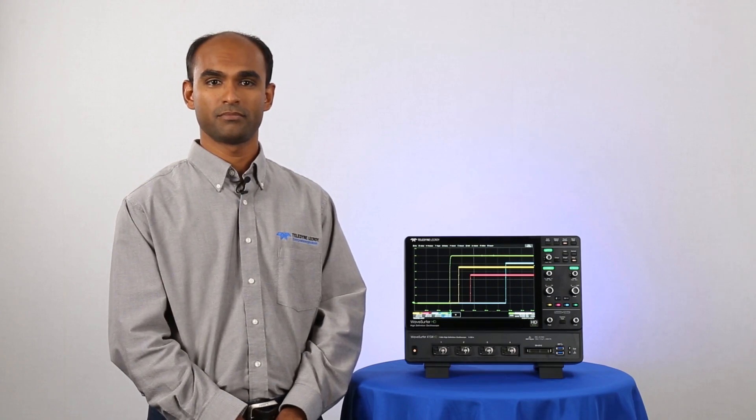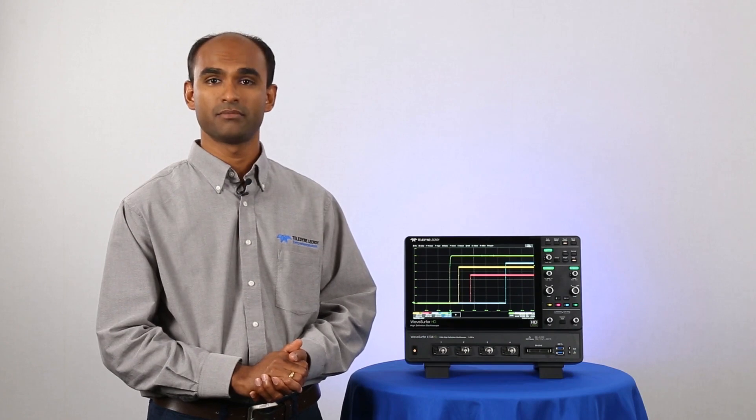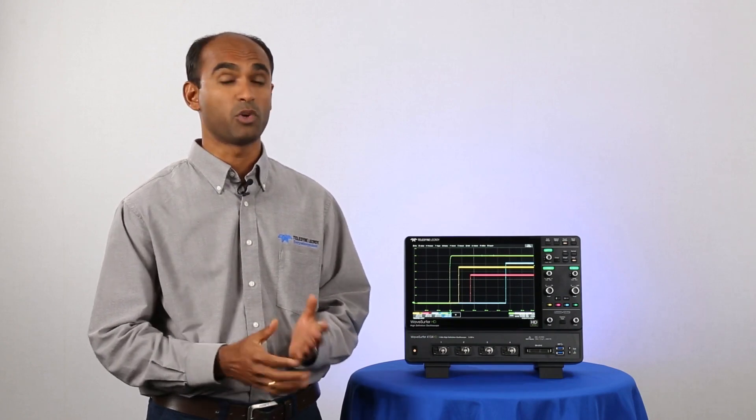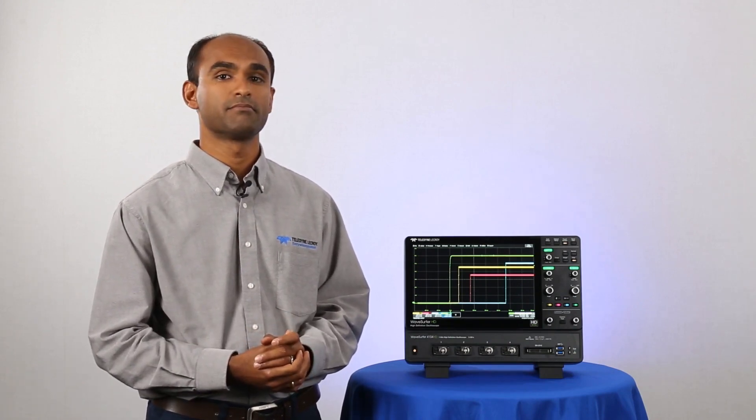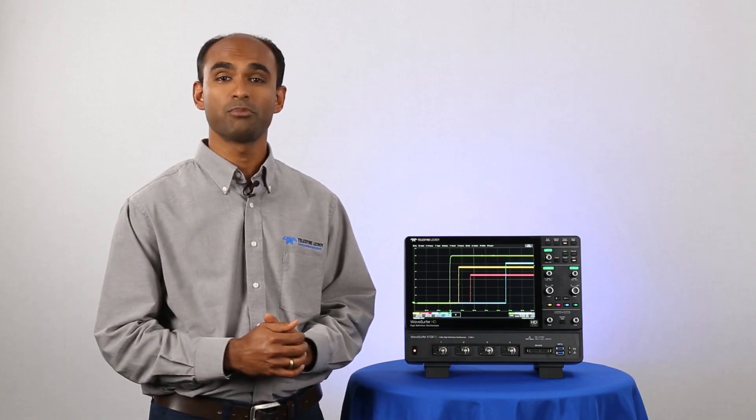How about for 5 kV apparatus? We have that as well. What's the common mode? It's 6 kV. What's the differential swing of that? 7.6 kV. And the CMRR and the gain accuracy, is it worse than the other probes? No, it stays the same as the 1 kV probe.